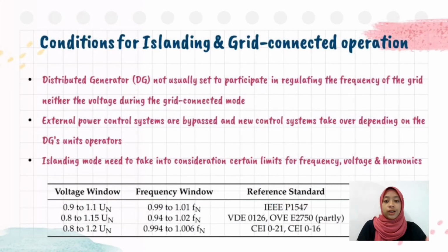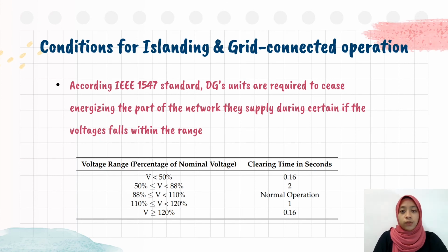Alright, let's move to the conditions for islanding and grid connected operation. DG is not usually set to participate in regulating the frequency or the voltage of the grid during grid connected mode. The external power control systems are bypassed and a new control system takes over, depending on the DG unit operators. The islanding mode needs to take into consideration certain limits for frequency, voltage and harmonics. As shown in the table below, there are certain limits for voltage, since I am doing voltage control. Mostly, people follow the IEEE 1547 standard. According to it, DG units are required to cease energizing the part of the network they supply within a certain time if the voltage falls outside the range.